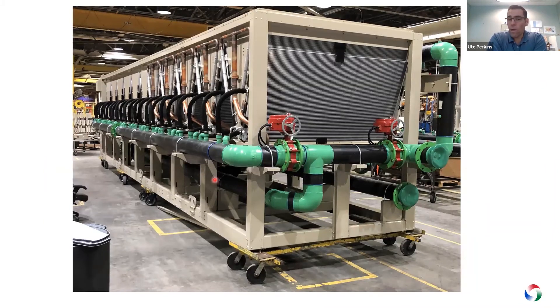The next part of our design is the coil — our free cooling coil. We use a coil on top of a coil: our condenser refrigerant coil is set right behind our free cooling coil. They're both microchannel. We're big believers in microchannel based on performance. As we were developing this, we used standard microchannel but our pressure drop wasn't where we wanted it to be. We went back and pushed our vendor to provide an alternative, and they came back with a microchannel coil where the microchannels were slightly enlarged, so our pressure drop went down significantly.